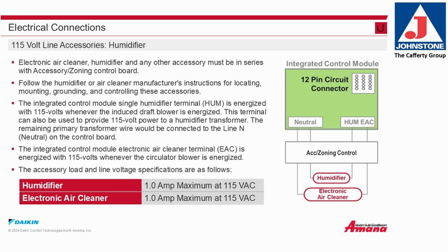Electrical connections. 115-volt line accessories, such as humidifier or electronic air cleaner. Electronic air cleaner, humidifier, and other accessories must be in series with the accessory/zoning control board. Follow the humidifier or air cleaner manufacturer's instructions for locating, mounting, grounding, and controlling these accessories. The Integrated Control Module Single Humidifier Terminal, designated HUM, is energized with 115 volts whenever the inducer draft motor is energized. This terminal can also provide 115 volts to a humidifier transformer if you are installing a humidifier with a 24-volt solenoid. The remaining primary transformer wire would be connected to the line neutral on the control board.